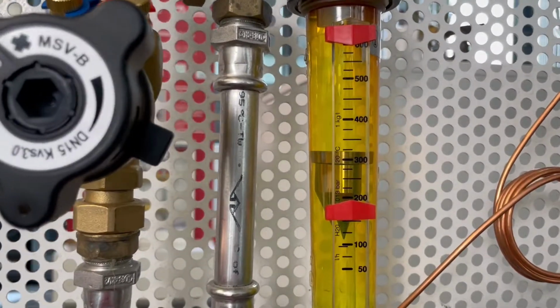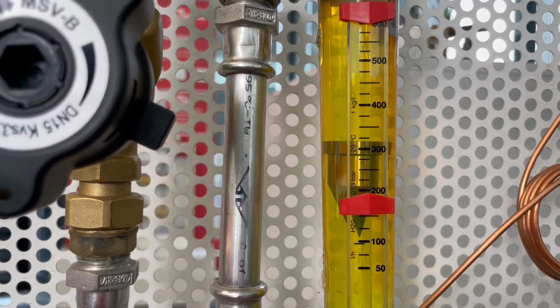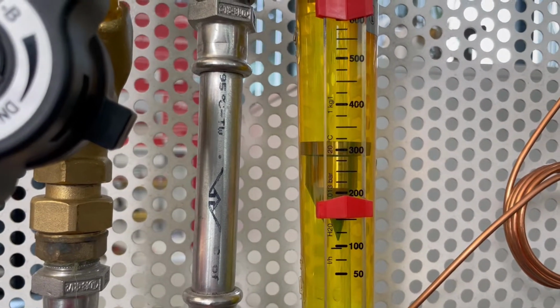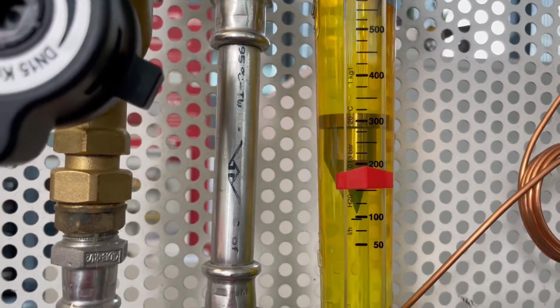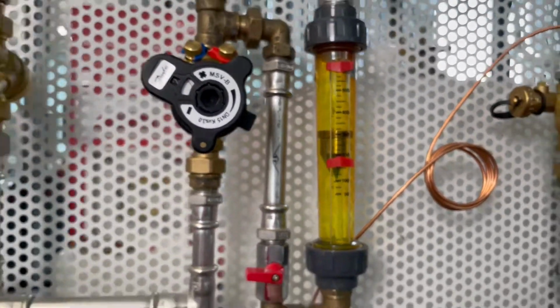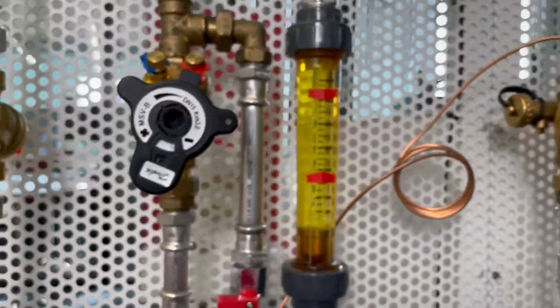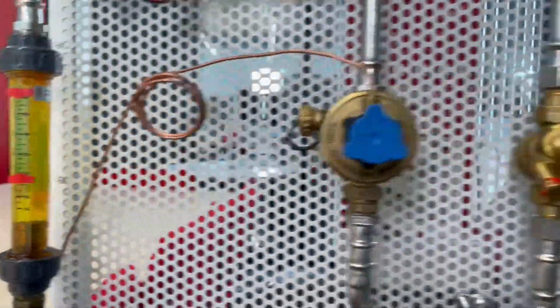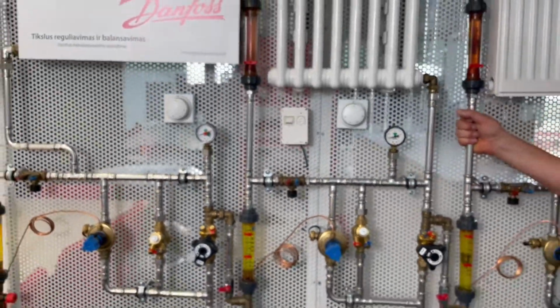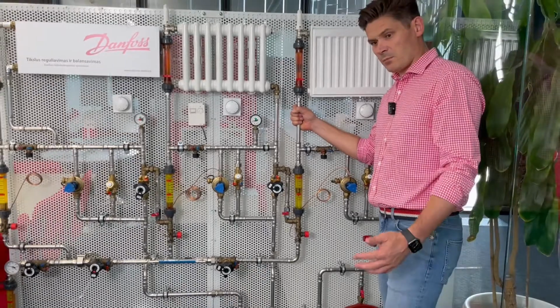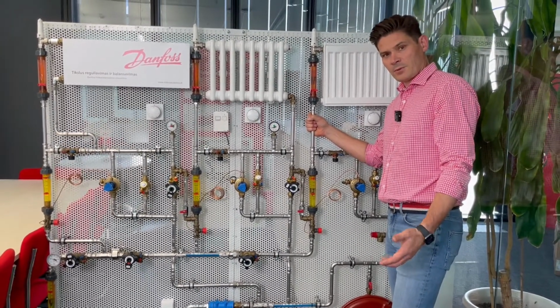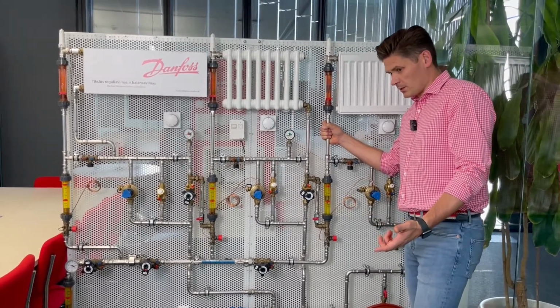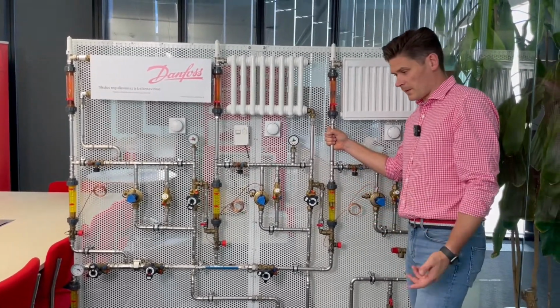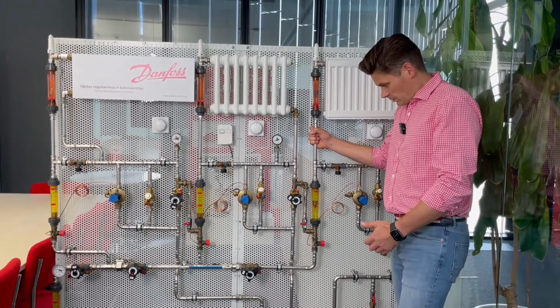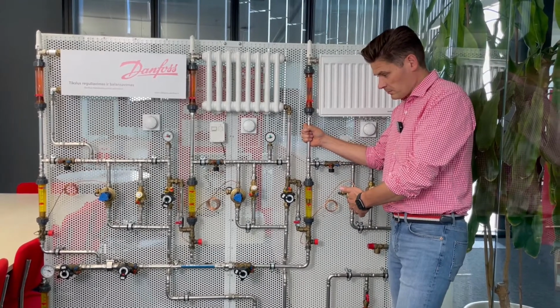Oh my God, what do we have? We have overflow again. Maybe not so big, almost the same actually, but a little bit less. With the 3-speed pump it was 350 liters, with the automatic pump it is 320 liters. Riser number 2 is closed, riser number 1 is also closed. What to do? It looks like we did what somebody advised. We put in an electronic pump which should react to our thermostats and reduce the speed of the motor and deliver less flow, but it seems it doesn't work.